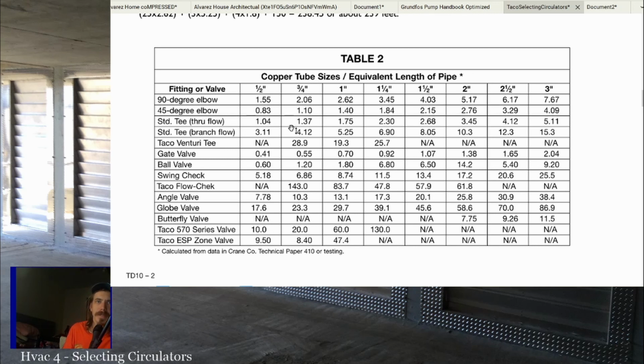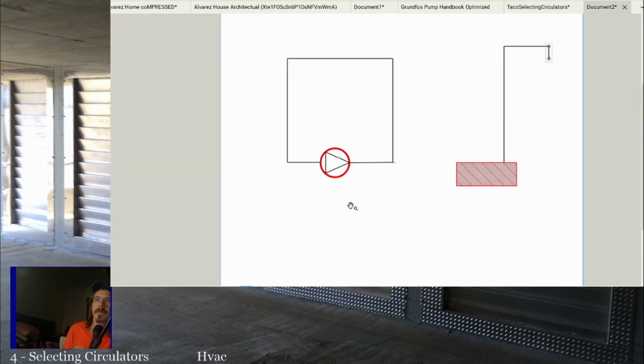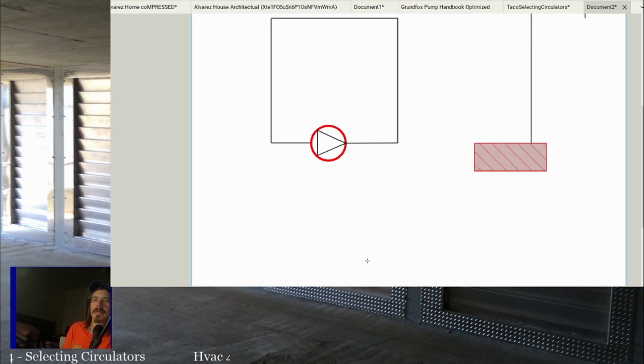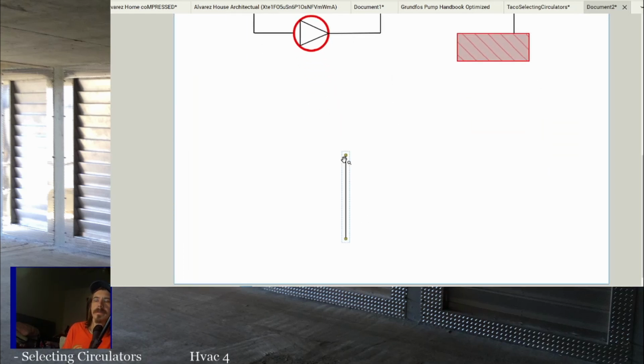Everything else is kind of just nickel and diming you. A 3/4 90-degree elbow is 2 feet each one. So it's not that much more, but if you have a bunch of them in the system, it's going to add up. Your T's, they have through flow and branch flow. If you just go straight through the T for the main run of the circuit, that's 1 foot, or 1.3 feet. If you're going 90 in the branch and run of the T, so if you're looking at a T, right?